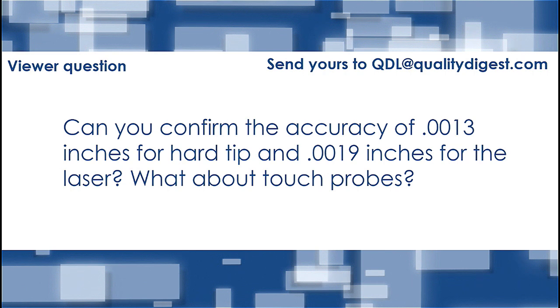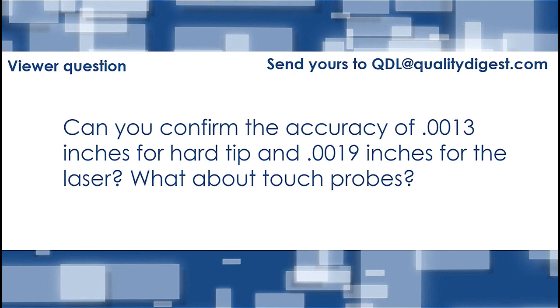Okay, can you confirm the accuracy of 0.0013 inches for hard tip and 0.0019 inches for the laser? What about touch probes? Good technical question. Yeah, so that accuracy is spec'd to the new ISO standard, and you can confirm it on your own with a gauge block. We measured that a few times, and once you get your arm, you can verify that it's within spec, and that's the volumetric accuracy, so that's moving the arm through its entire range of motion.